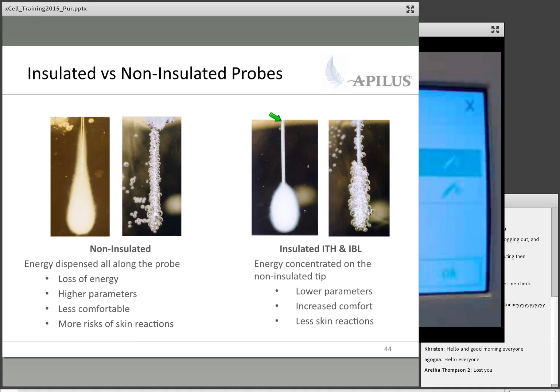So if you're doing thermolysis, for example, now you can see that this is covered in some sort of insulation. So no current can go through this, not unless you essentially blow out through the insulation, which can definitely be done if you have too high of parameters. But all the energy is concentrated at the tip. You have no loss of power up here. So in order to create this wide of a heating pattern, I don't need as much energy. So my parameters will be lower. And because my parameters are lower, it's more comfortable and I have less skin reactions because no energy is up here. With the blend, it's the same thing.